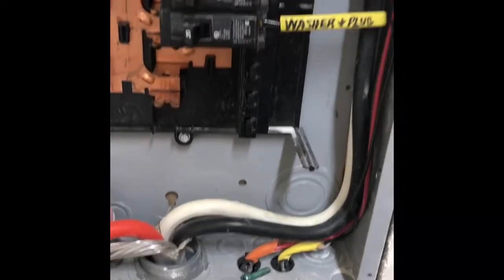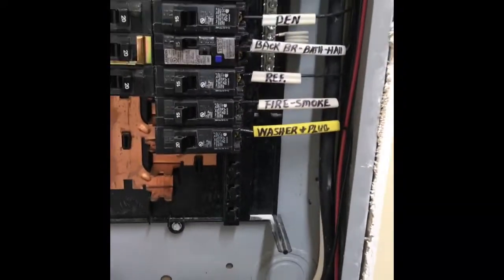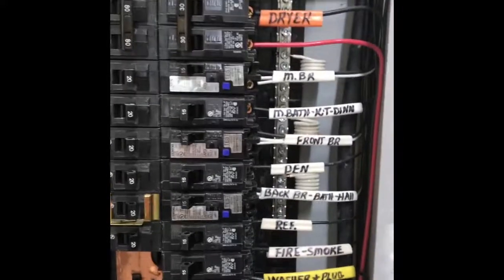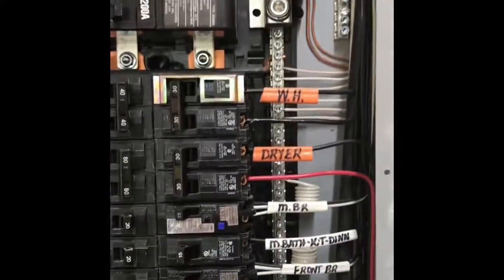The big difference between a distribution panel and a main panel is on the distribution panel or a sub panel, such as this one, is the grounds. That's going to be all your bare copper, and sometimes your braided aluminum for your bigger appliances. But they have to be isolated. They can't be bonded to your neutrals on your neutral bars.